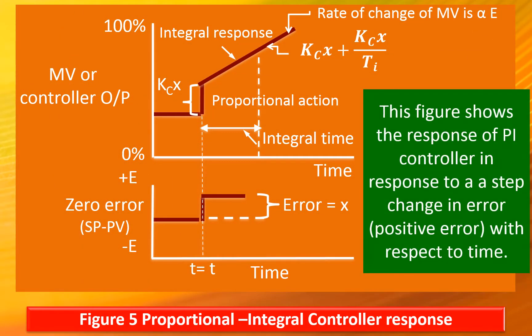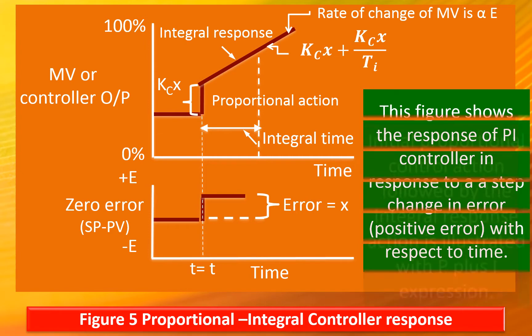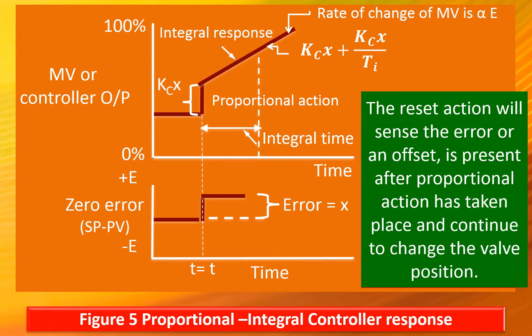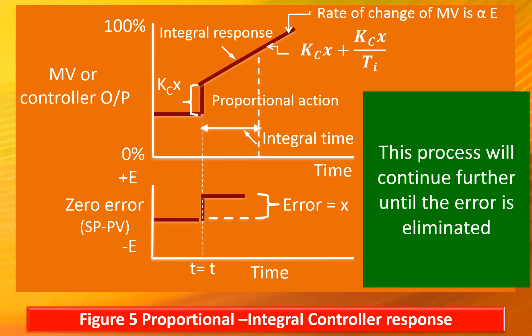This figure shows the response of a PI controller in response to a step change in positive error with respect to time. Initial proportional control action followed by the integral response action is illustrated with the P + I expression. The reset action will sense the error or offset present after proportional action has taken place and continue to change the valve position. This process will continue until the error is eliminated.